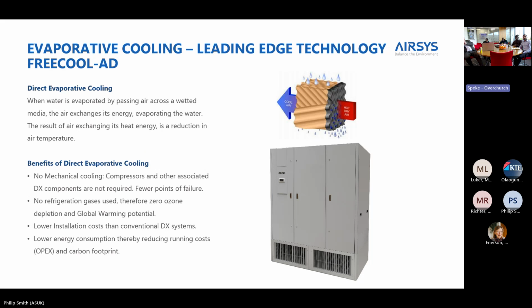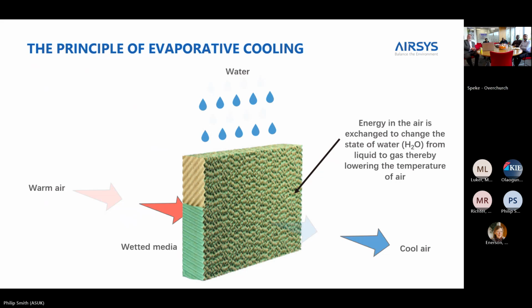As I touched on earlier, one day refrigerants will be banned, or disappear, unless they change their perspective in the years to come. Evaporative cooling then becomes a means by which you can provide reasonable cooling to a degree throughout the year. We make a particular product called the AD. The principle is, I'm sure, one you're aware of: the evaporative pad and blowing air across it. So basically, we have a nice little pad, our warm air going across, and some water, and some nice cool air going into the room.